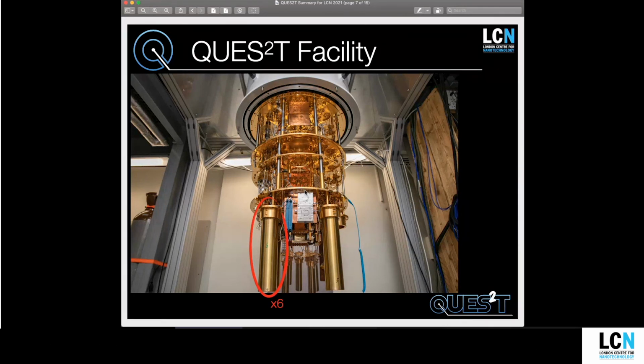So a way a user engages with this facility is the user places their device, their sample, within one of these sample boxes, and either uses existing measurement equipment that's in the racks or provides their own. The system needs to be opened up. Users attach their sample, the system then gets closed down, and on a typical run, it remains cold for about 2 weeks, in addition to a few days to warm up and a few days to cool down. So in using this system, you're committing to approximately a 3-week run.